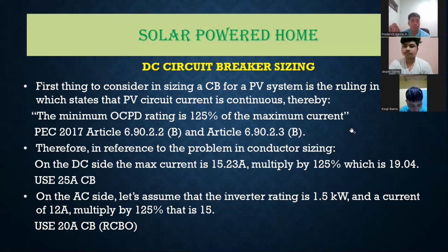So now we have DC circuit breaker sizing. The first thing to consider in sizing a circuit breaker for a PV system is the ruling in the Philippine Electrical Code, which states that a PV circuit current is continuous. Thereby, the minimum OCPD rating is 125% of the maximum current. PEC 2017 Article 6.90.2.2(B) and Article 6.90.2.3(B). Therefore, in reference to the problem in conductor sizing, on the DC side, the max current is 15.23 amps multiplied by 125%, which is 19.04, so use a 25 amp circuit breaker. On the AC side, let's assume that the inverter rating is 1.5 kilowatts and a current of 12 amps multiplied by 125%, that is 15. We use a 20 amp circuit breaker.